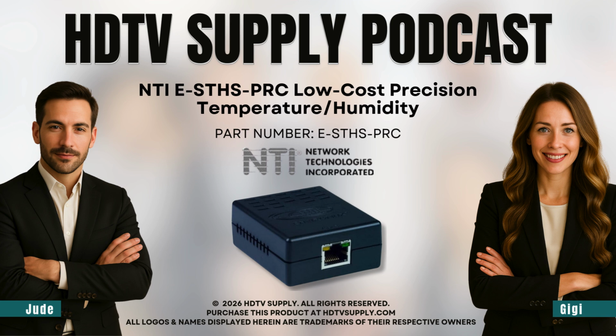It's RS-485, and that runs over standard network cable - CAT5, CAT6, the stuff that's already in the walls everywhere. And that setup allows for a cable run of up to 1,000 feet. 1,000 feet? That's over 300 meters. So why is RS-485 so good at that distance? It's all about how it sends the signal - it uses what's called differential signaling.